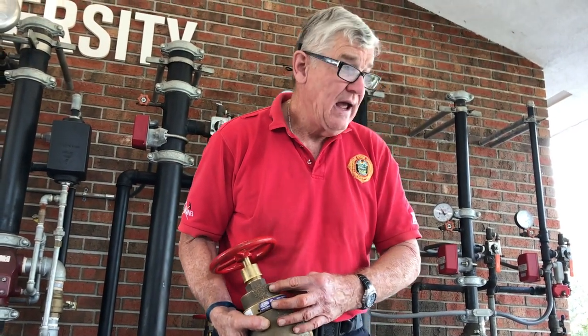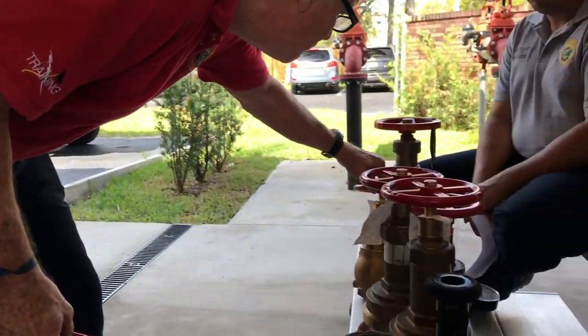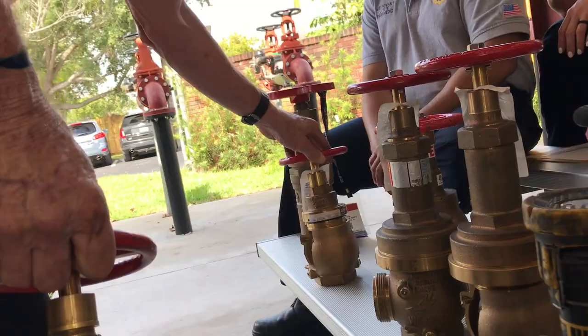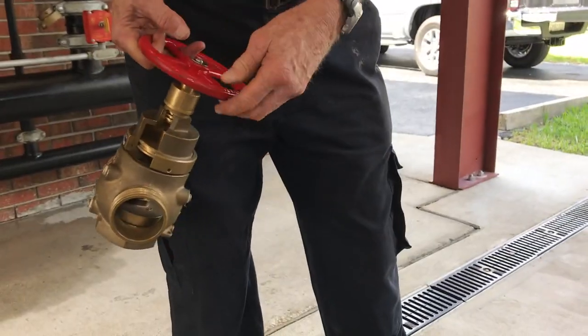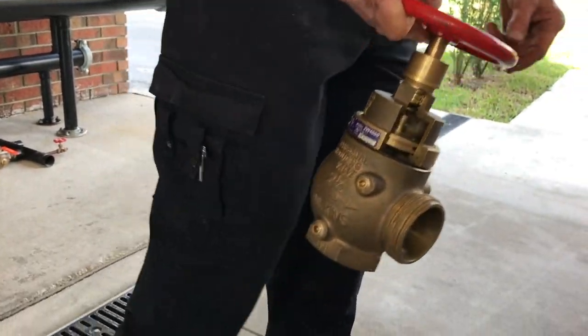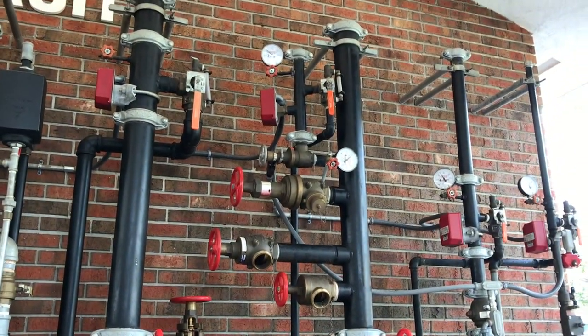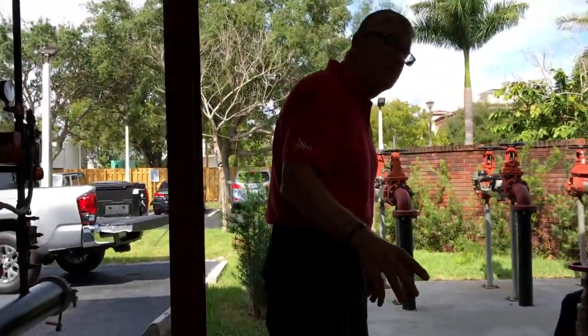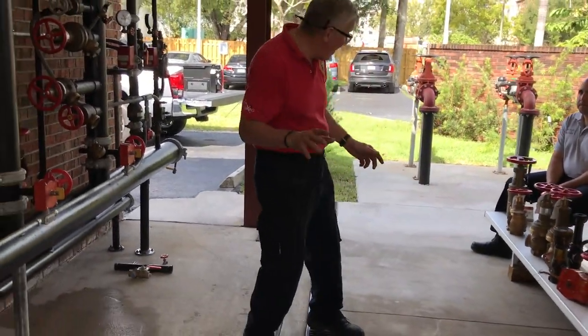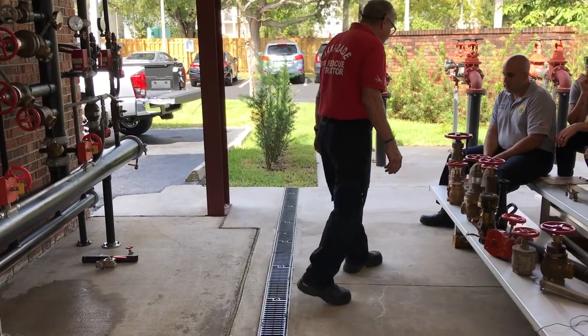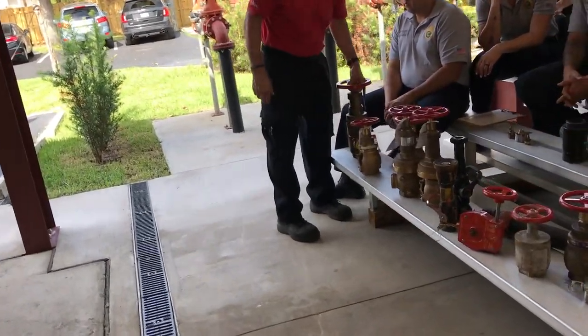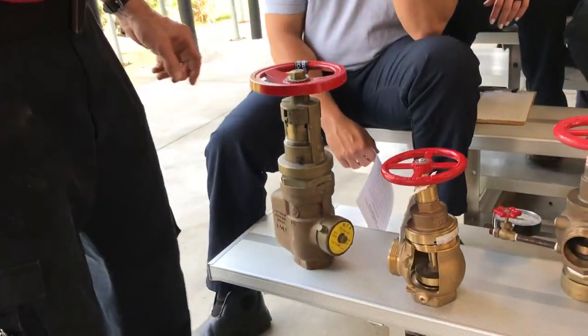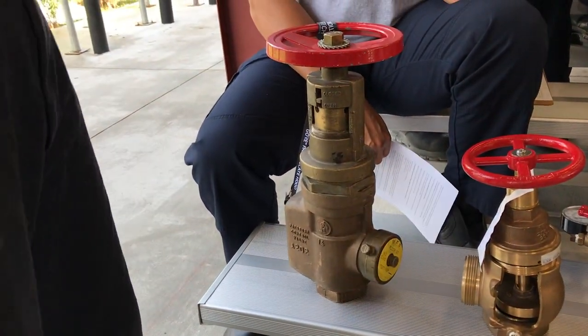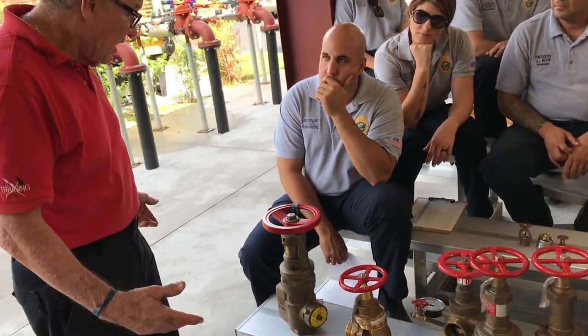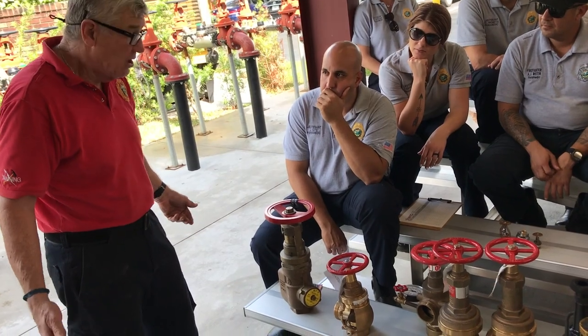This is a type Q. This device here happens to be a type S. Q obviously has more pressure reducing effect than the S. Now, that is a factory set. That is one type. The other type is field adjustable, sometimes referred to, in some cases, as fireground adjustable.